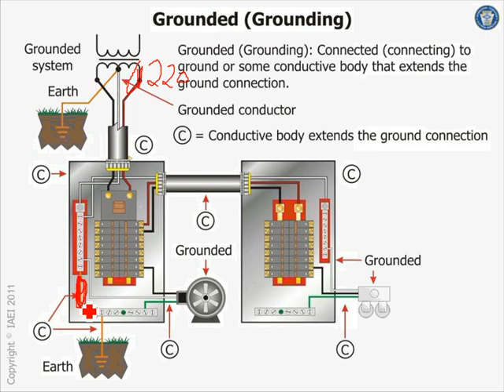But the advantage of what, I know exactly why we do it this way, especially in a single-phase system. We use that 240, 120 split power system, which is unique. You lose a neutral, you burn equipment, no question asked. But if I lose a neutral right here, a storm came and knocked down the 3 wires coming to the house, knocked down one of them, and it happened to be the neutral. Could it happen? Or a squirrel chewed right through the neutral. So now we lost a neutral. If you don't have this, you literally burn the house.